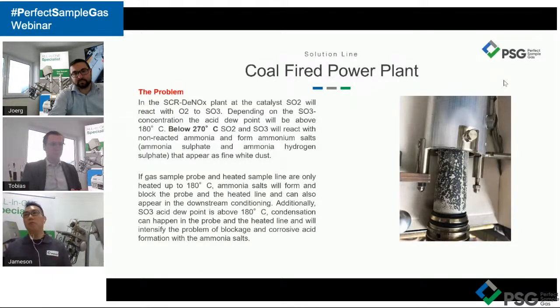because there are many people who understand that there is a high dust, so they do a back purge. It is very silly to do a back purge at the sample probe, because in any sample probe where you do a back purge, even though you have very high temperature instrument air, there is a tendency of cooling down. So this is a photo that you see: the powder is not dust. In fact, it is ammonium sulfate. So over here, in this probe, it is a mistake that some customers have made.